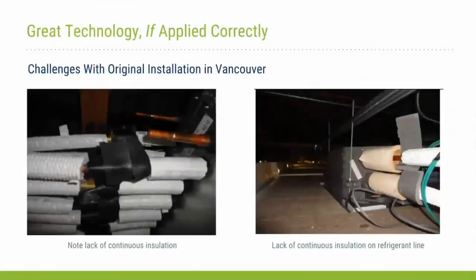So here's some examples of poor refrigerant installation. So that vapor barrier isn't sealed, so you have an opportunity to sweat. It was just not done well. So on the right is the cassette unit itself. On the left, I believe, is the branch controller. So lots of opportunities for sweating above the space. And if you look at it, they actually used a flexible refrigerant line, which could be like spaghetti going through the space. It was a little concerning. They weren't nice clean lines. So it was good for installation, easy installation, but in terms of trying to make sure we know where those lines are and we don't hit them in the future, it's a bit of a concern. Next slide, please.